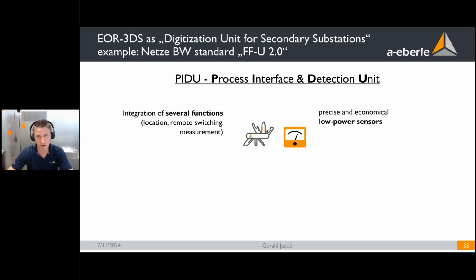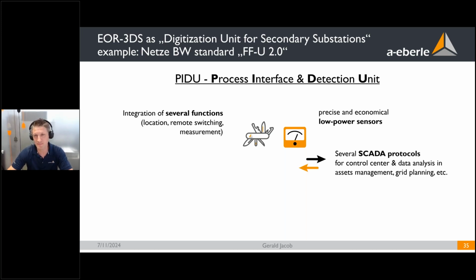The devices should be compatible with available, precise, and economical low power sensors. They really wanted to have such bushings with integrated sensors, from ABB or from Siemens. The demand was to have several SCADA protocols in parallel. We will see that also on the next page. So the data from the devices should not only be available in the central SCADA system, but also in other systems, in some kind of IoT system, for example, for asset management and grid planning.